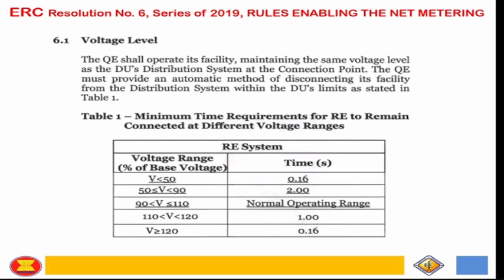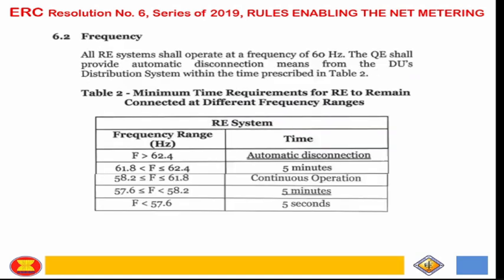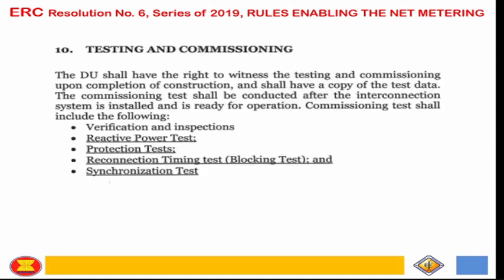And then the voltage level settings, no, this is the minimum time requirement for the inverter to remain connected at different voltages, different voltage ranges, no. So based on the percentage, kailangan yung protection mo is coordinated, no. It's less than the time requirement, or else magkakaroon ka ng impact with the distribution system. And then the frequency is the same, no? Ito yung mga time requirement, no, na makapag-sustain siya at still remain connected with the distribution system.